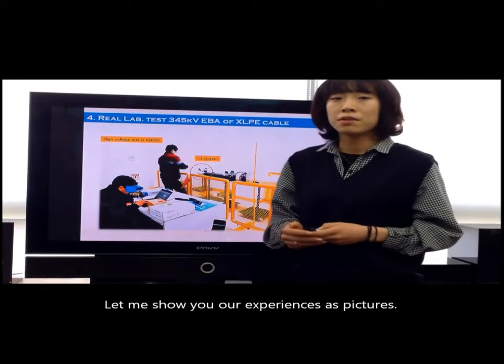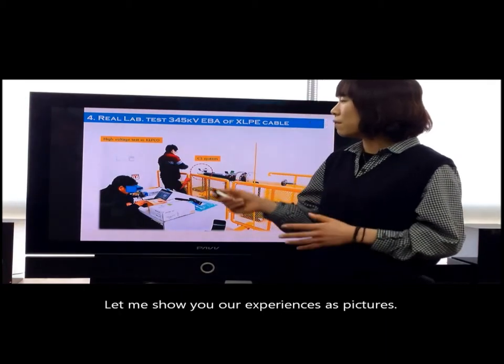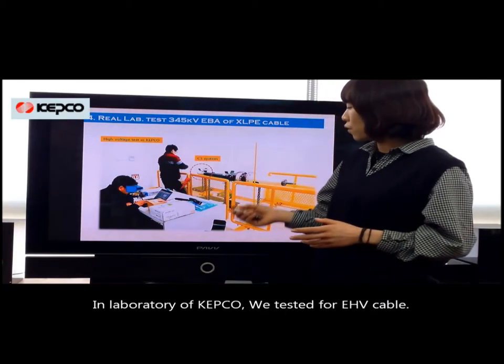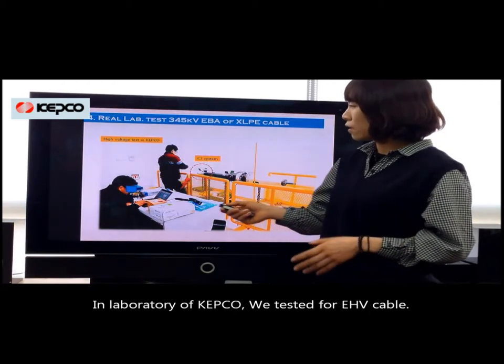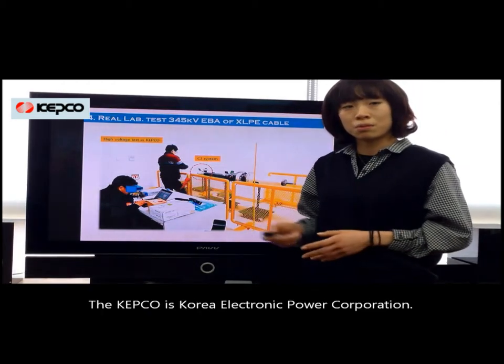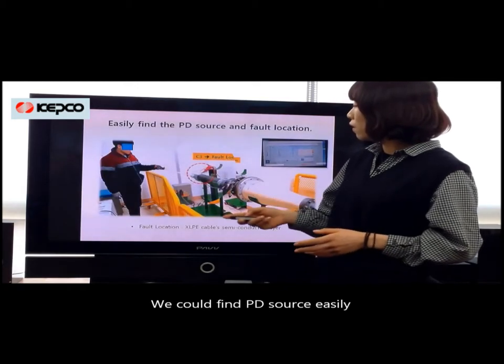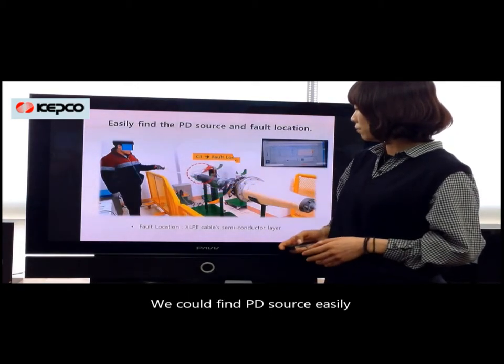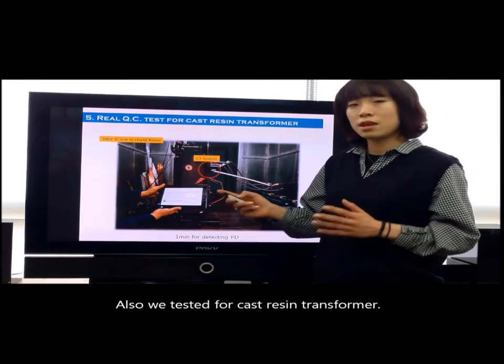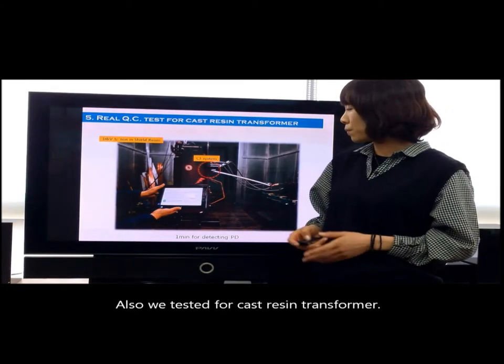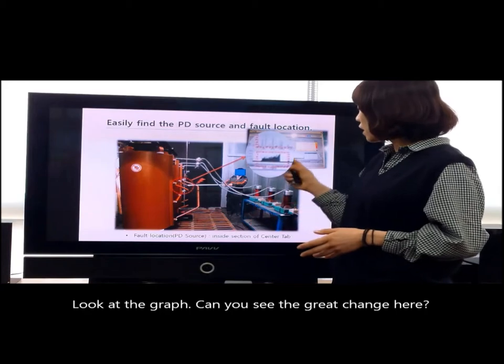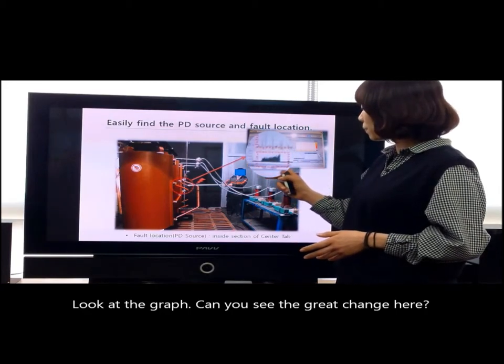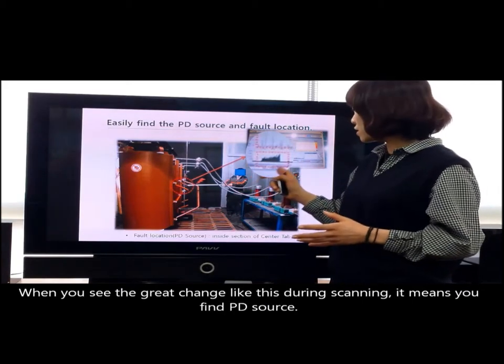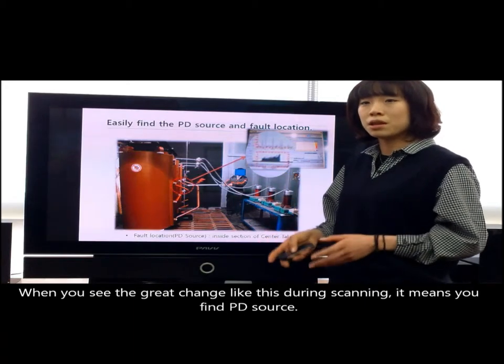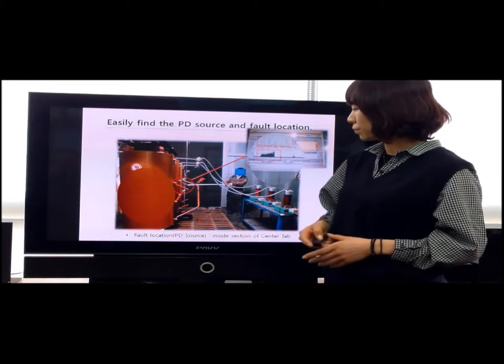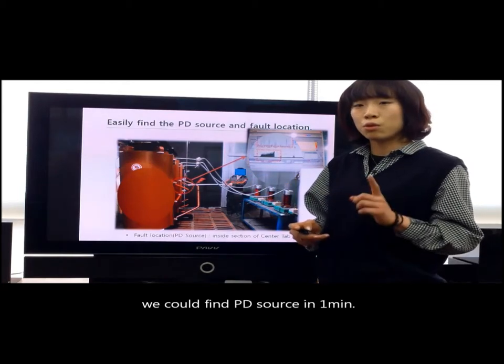Let me show you our experience as pictures. In the laboratory of KEPCO, we tested an extra high voltage cable. KEPCO is Korea Electric Power Corporation. We could find the PD source easily. Also, we tested a cast resin transformer. Look at the graph. Can you see the great change here? When you see the great change like this during scanning, it means you found the PD source. We could find the PD source in 1 minute.